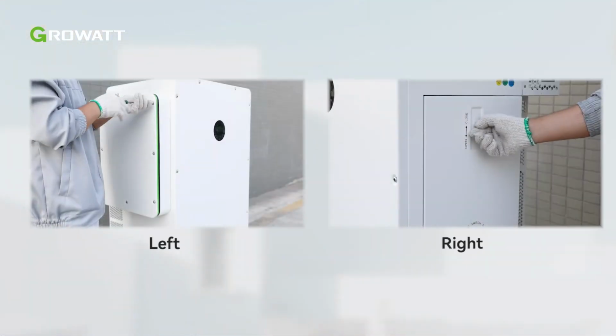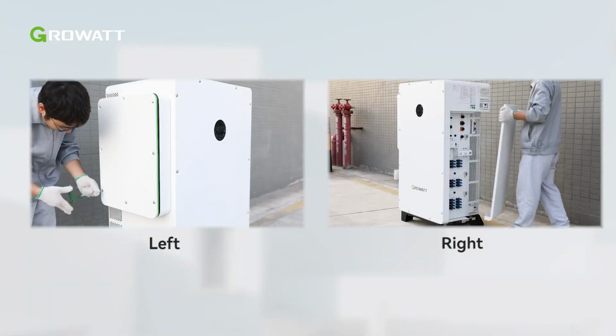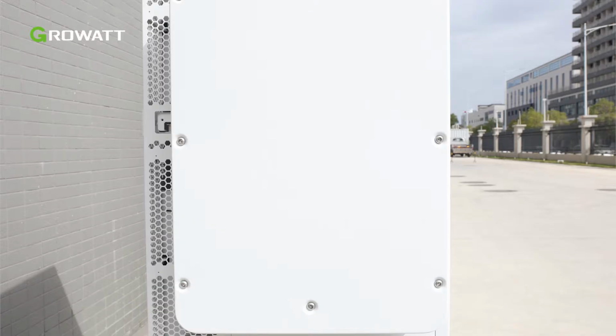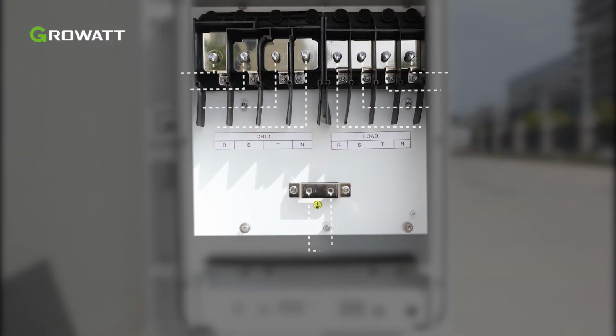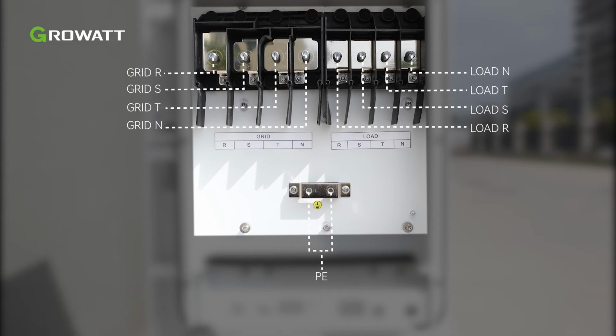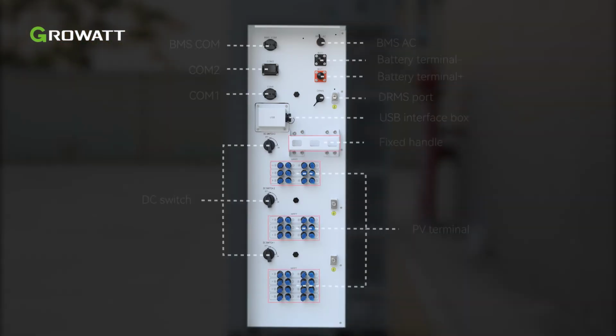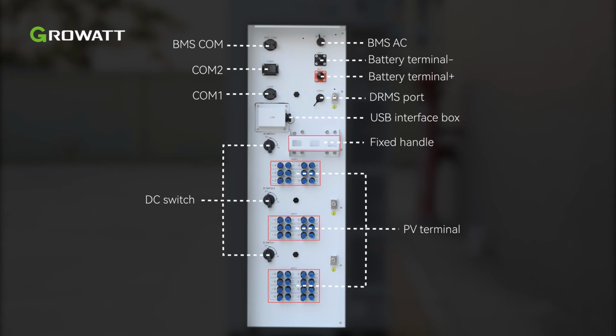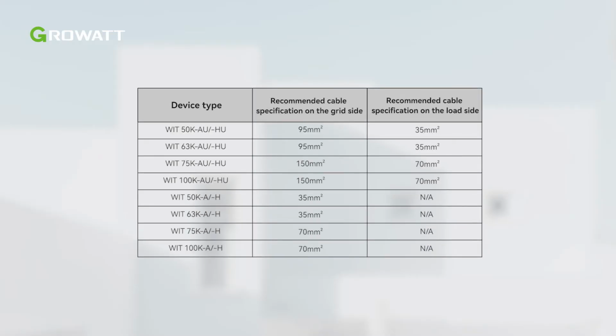Remove the left cover plate and right cover of the WIT to prepare for wiring. Before wiring, check the following terminals on the left side panel of the WIT inverter. On the right side panel of the WIT inverter, the following terminals are located. The rated circuit breaker and power cable specifications are illustrated in the table. Please choose the appropriate breaker or cable according to the inverter model.